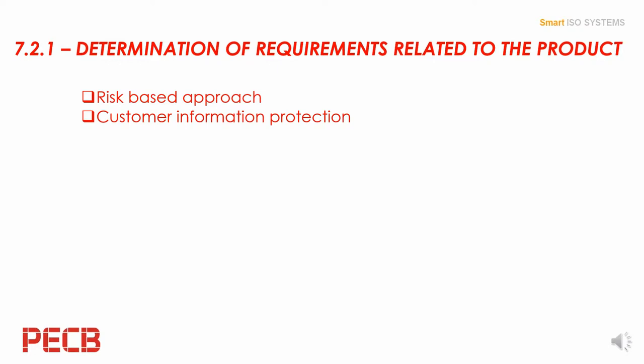Determination of requirements related to the product. The main element that changes in this section, which is under 7.2, customer-related processes, is the addition of a requirement to determine user training to ensure that a product will be used in a safe and effective manner. By user, it means the physician or the person who will install the device. While training is sometimes taken into account by manufacturers, it is not always done consistently. This change seeks to ensure that the training process gets firmed up and that there are more controls in place when it comes to training.